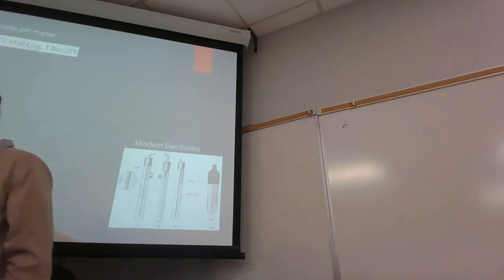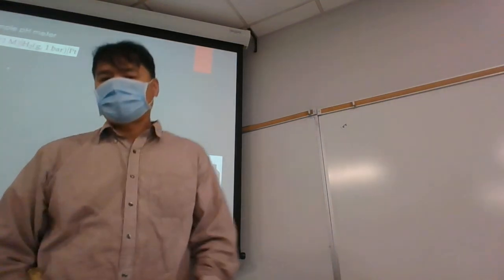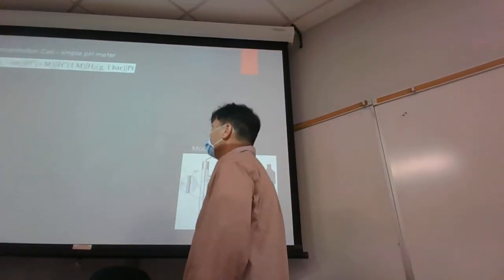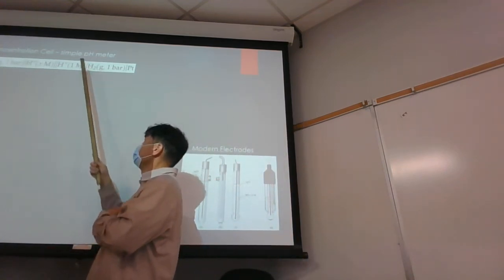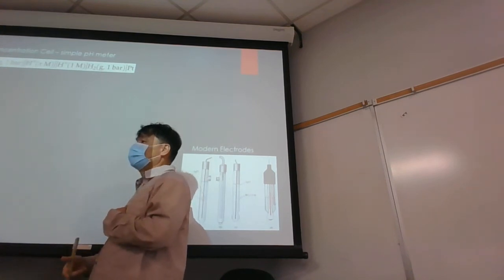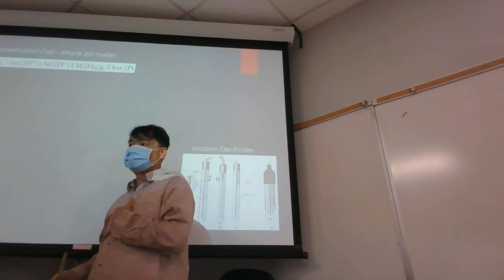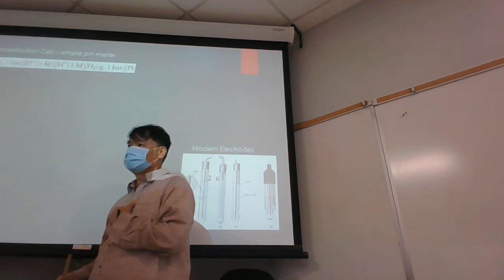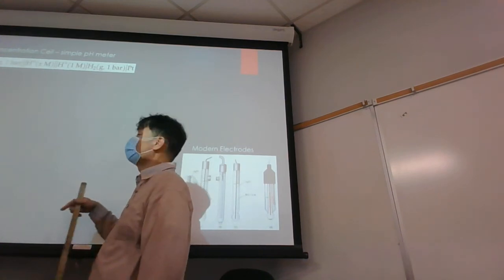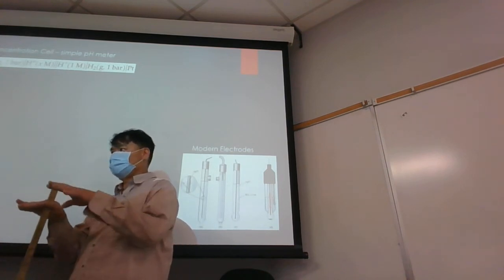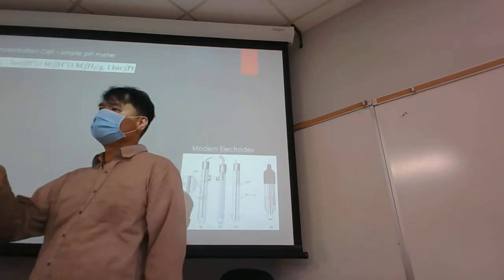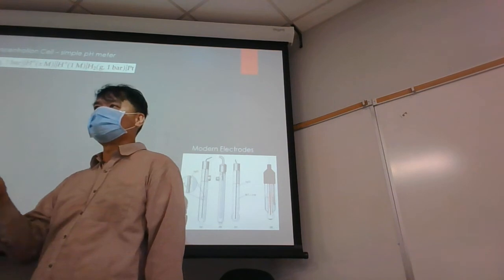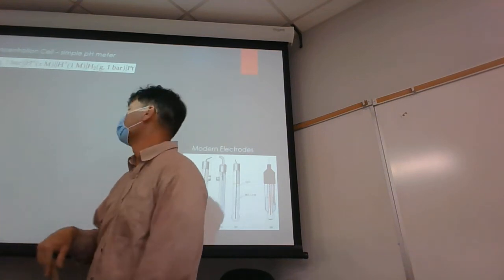Let's look at some applications of batteries. One application of electrochemistry is the pH meter. When you look at the pH meters that we have, the display of the LabQuest displays, in addition to pH, millivolts. What the calibration does is calibrate the millivolts with the pH. So you put it into a buffer, the pH meter just measures the millivoltage, and then you punch in the pH it's supposed to read, and it calibrates it that way.